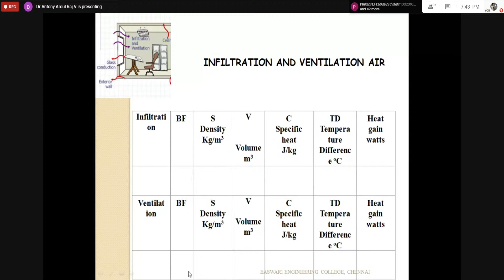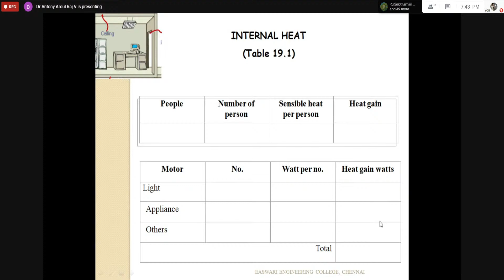Next I have internal heat. So you know how many people, what is the sensible heat per person, from the table we have just seen. Multiply, and mostly it will be constant. The motor, light, and other appliances mostly will be constant, except cooking appliances where there will be some variation. Computer, motor, fan, lighting, all these will be almost the same. Take the numbers multiplied by watt per number, you get the heat gain. Add all these things, and this is the internal sensible heat.